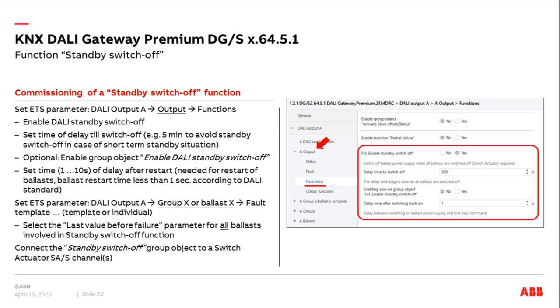Now let's go to the ETS parameters — it's not really difficult. First, go to the ETS parameters for the complete DALI output, such as DALI output A or B, and enable the standby switch-off function. Set the delay time for switching off. You can enable a group object to enable or block this function. Set the time after restart. Then go to the ballasts, groups, or templates and select the parameter 'last value before failure'. Then link the group objects.